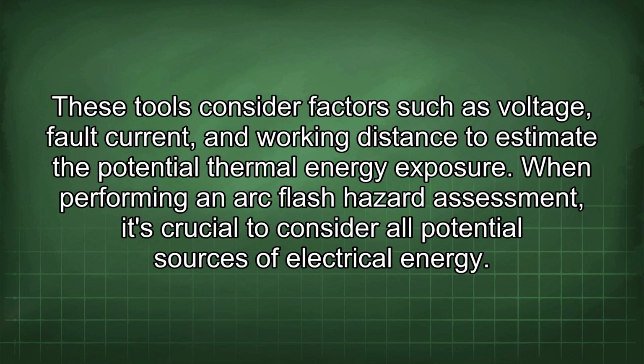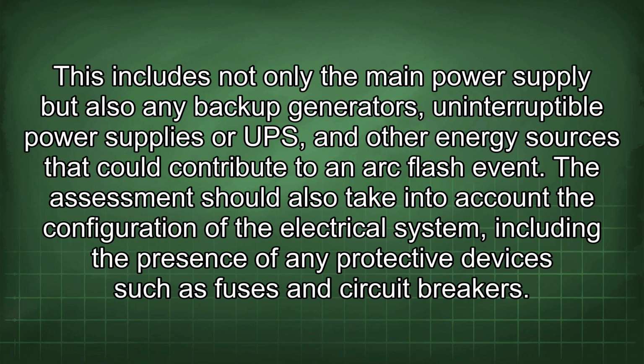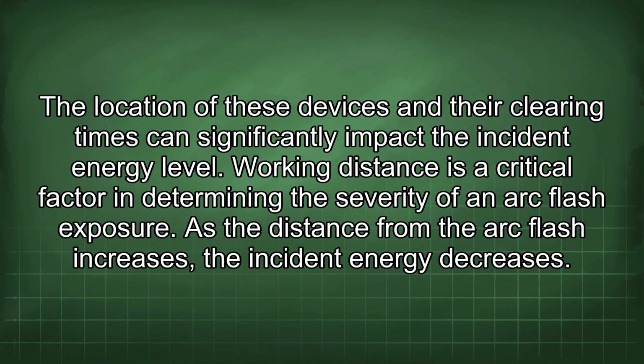When performing an arc flash hazard assessment, it's crucial to consider all potential sources of electrical energy. This includes not only the main power supply but also any backup generators, uninterruptible power supplies or UPS, and other energy sources that could contribute to an arc flash event. The assessment should also take into account the configuration of the electrical system, including the presence of any protective devices such as fuses and circuit breakers. The location of these devices and their clearing times can significantly impact the incident energy level.